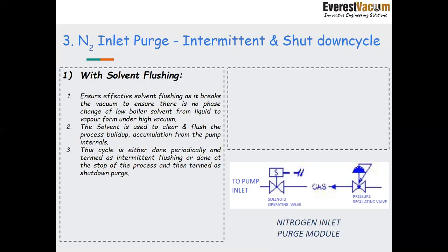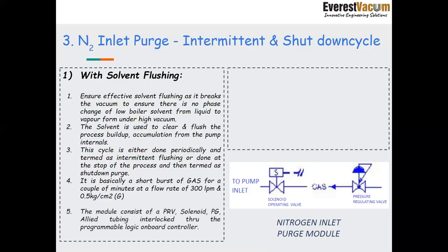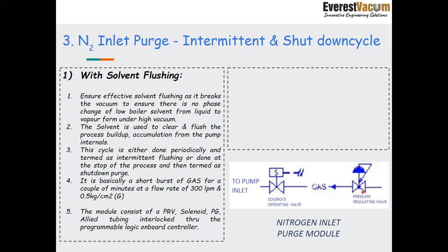certain days, but the process carryover keeps on accumulating into the pump, so that needs to be cleaned periodically, and that part is played via the intermittent flushing during the operation itself. So what is it? It is basically a short burst of gas for a couple of minutes at a flow rate of 300 LPM and 0.5 kg gauge pressure. The module consists of a pressure regulating valve and a solenoid operating valve interlocked through a PLC.